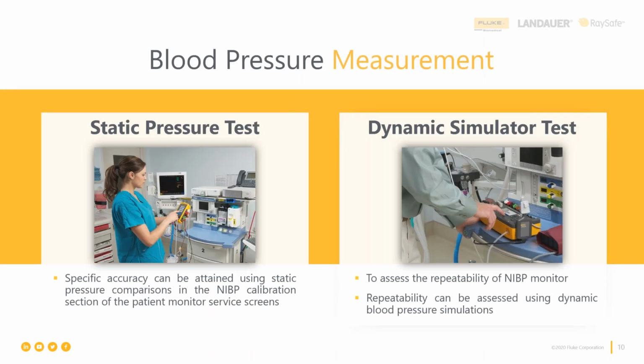Well, how do I know that? Again, we're talking about static pressure test versus dynamic, and the fact that you need to be able to control all of the variables and minimize, so you've only got one thing that you're focused on in order to get accuracy. So that's that. And then we've already talked about dynamic simulation. It's about repeatability and stability of the NIBP pressure measurement system in that patient monitor.